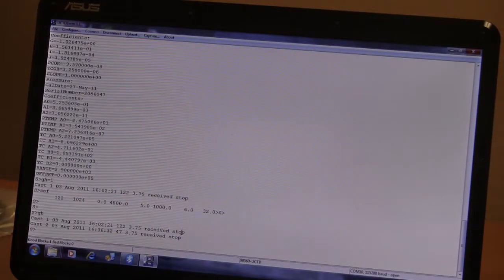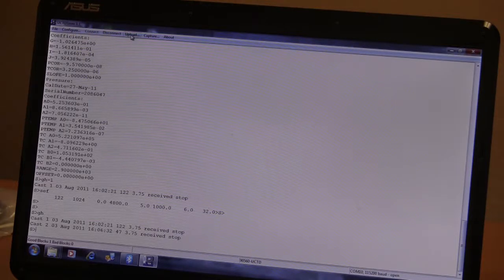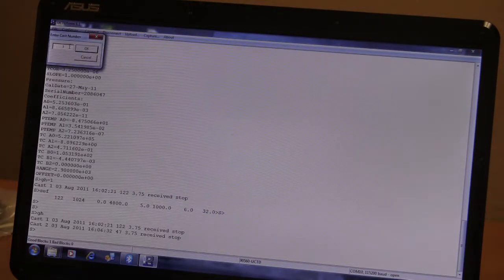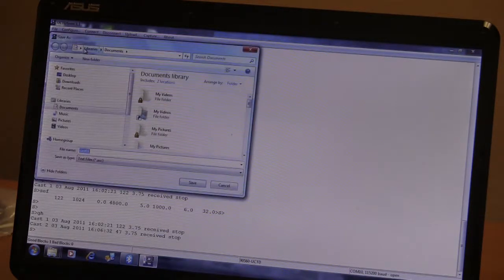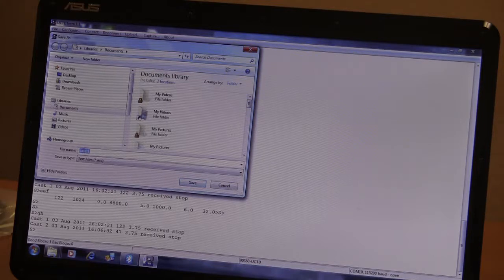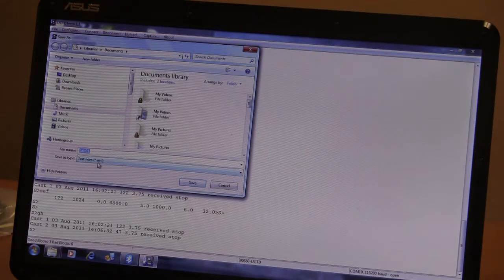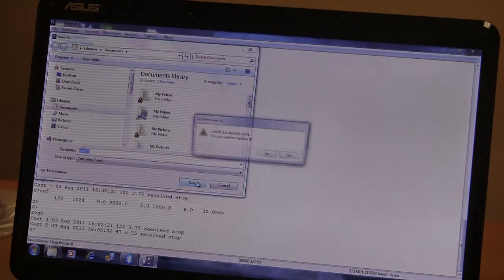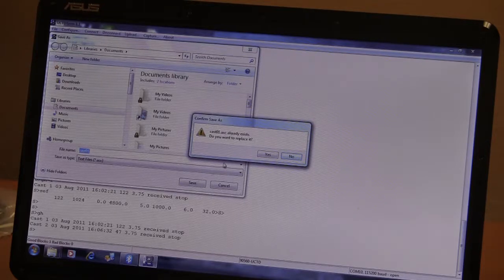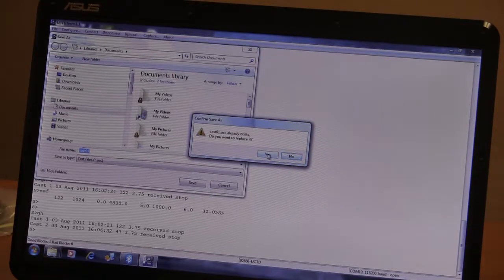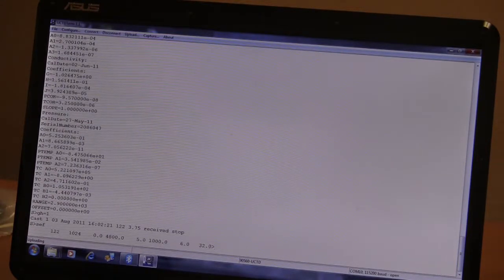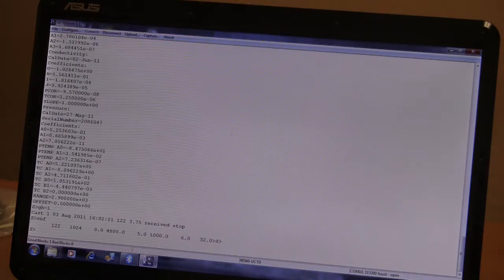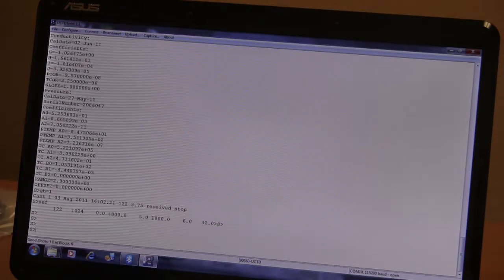In order to get the data off the probe, we use the upload command. Just press upload. You enter the cast number. In this case, I'm just going to choose one. Say okay. I'm going to give the file a name. There's no need to give an extension, it automatically will be added. You say save. Since that file exists already, it's going to ask you if you really want to replace it. In this case, I do. Now it's going to download the data. That data download is complete. You can see that because it's active again.